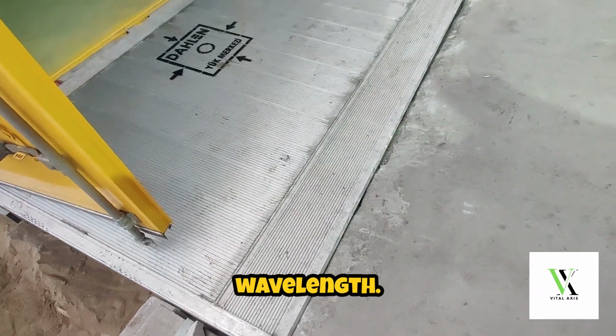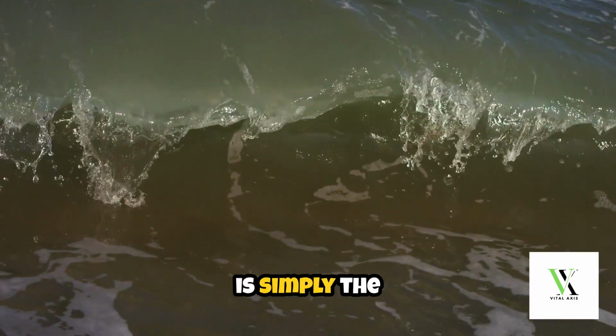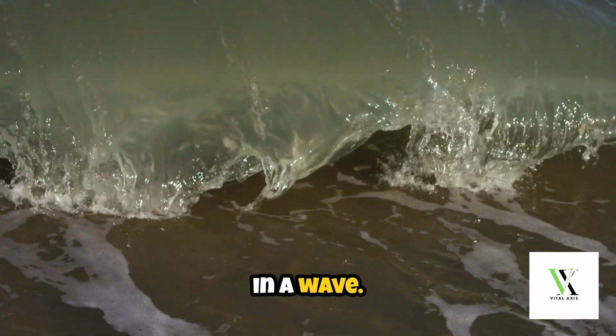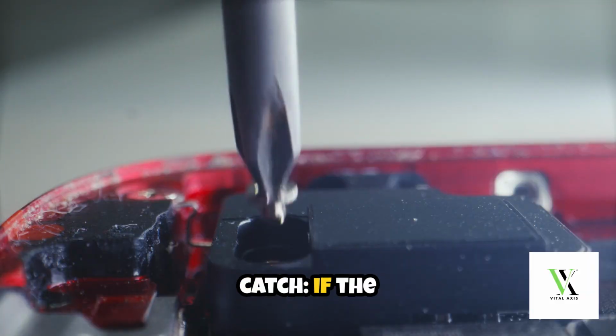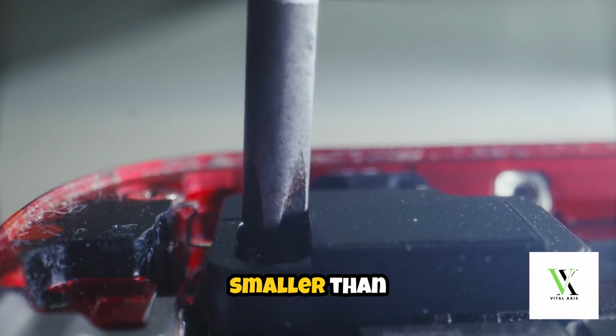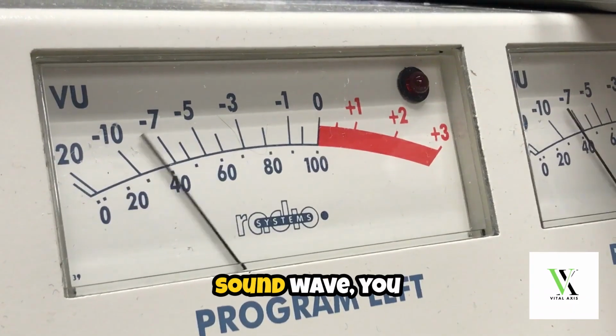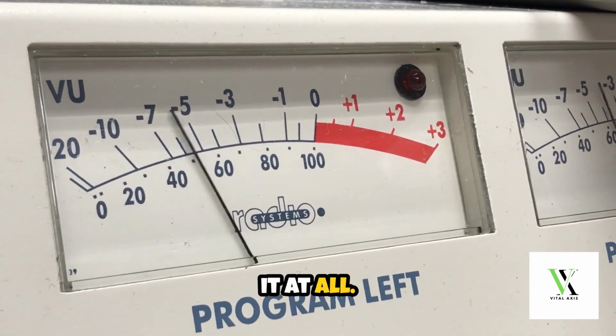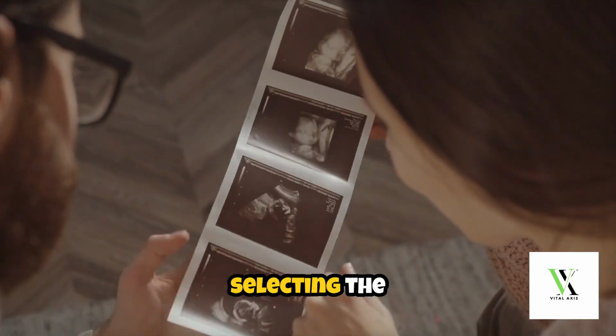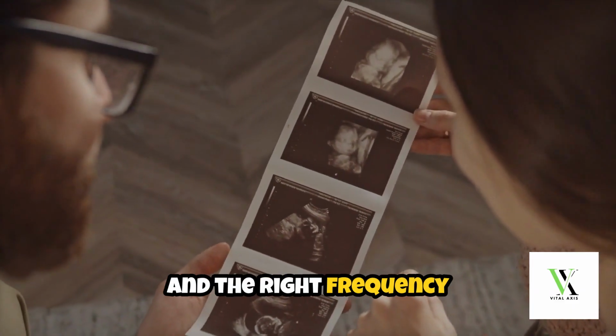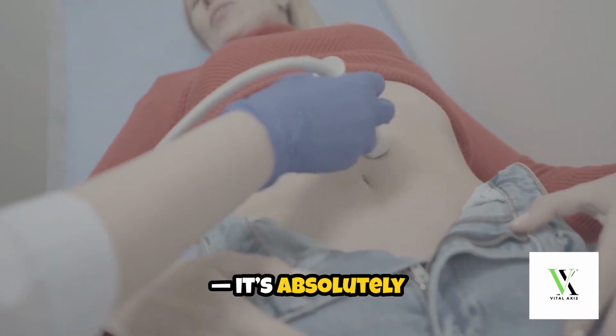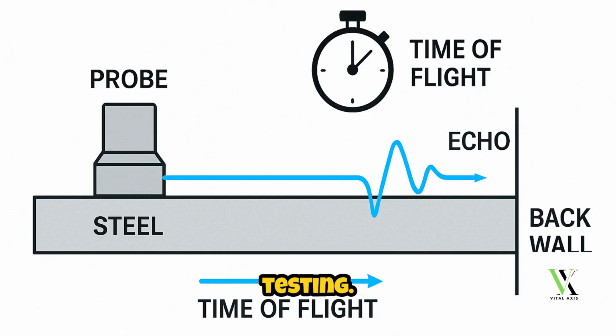Another key factor is wavelength. Wavelength is simply the distance between two peaks in a wave. But here's the catch. If the flaw you're looking for is smaller than half the wavelength of your sound wave, you might not detect it at all. This is why selecting the right probe and the right frequency isn't just technical, it's absolutely critical in ultrasonic testing.